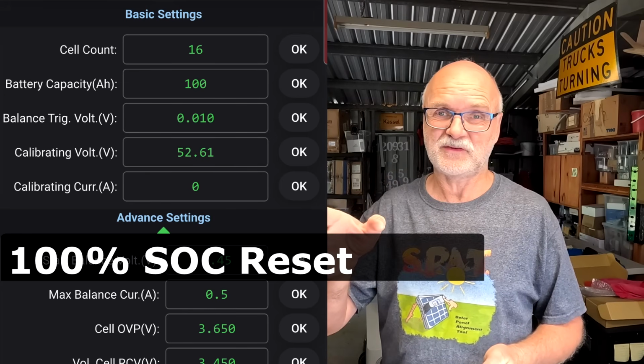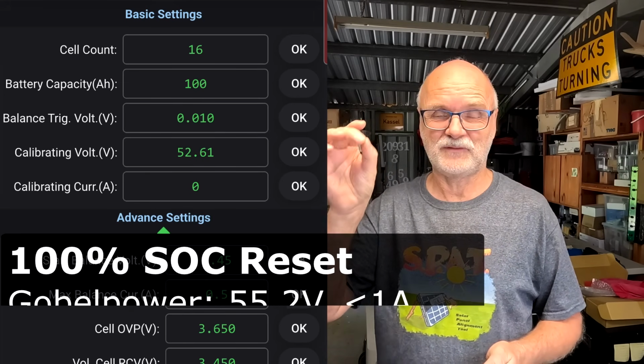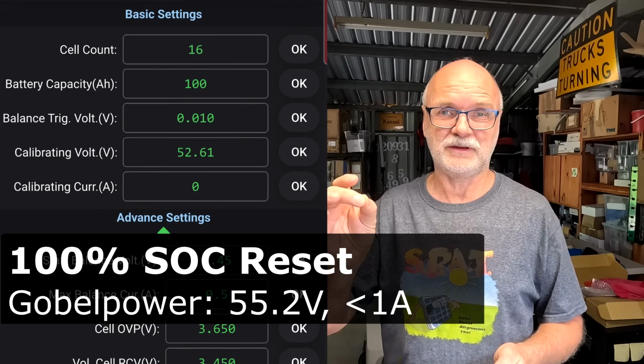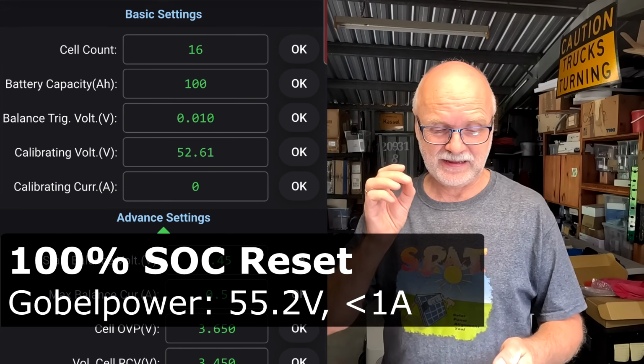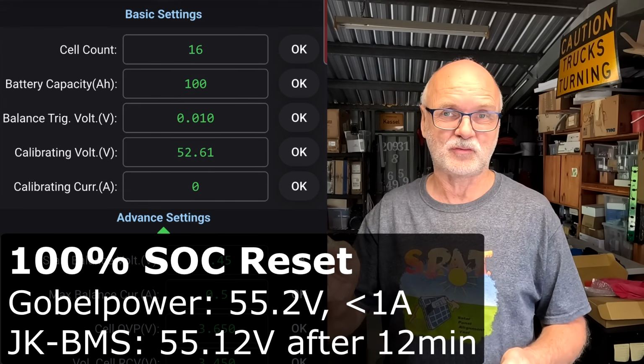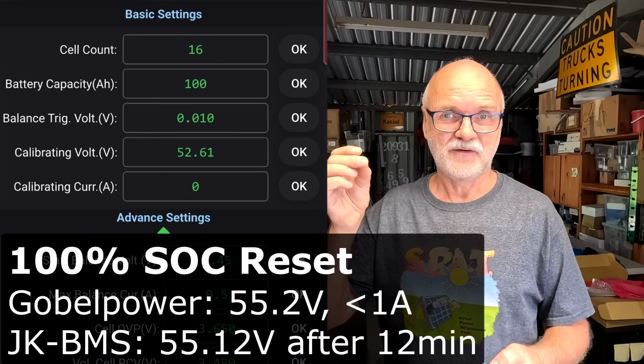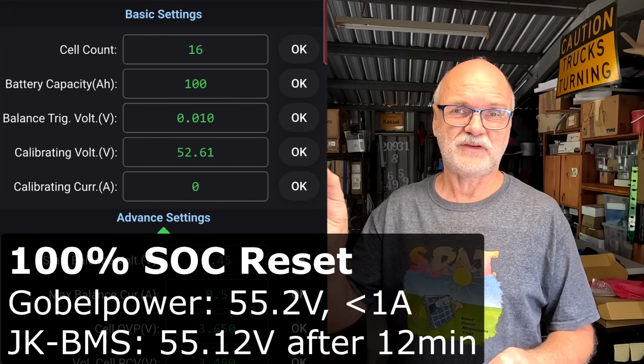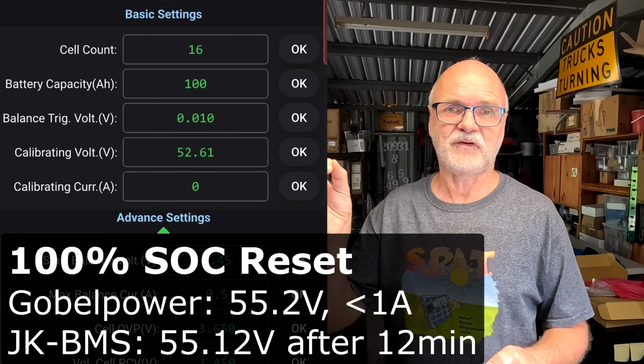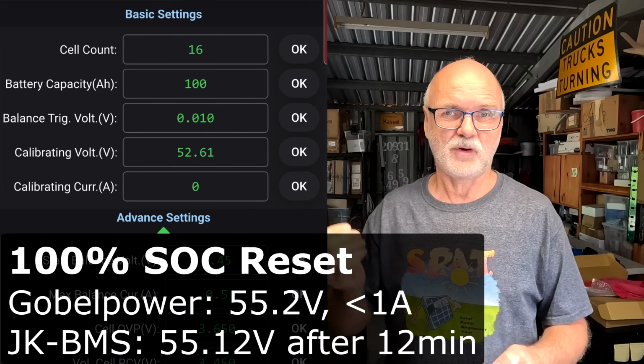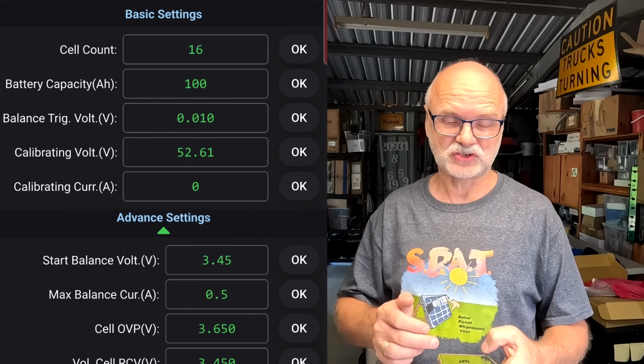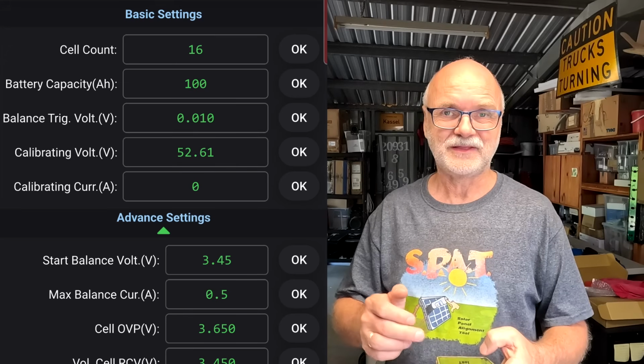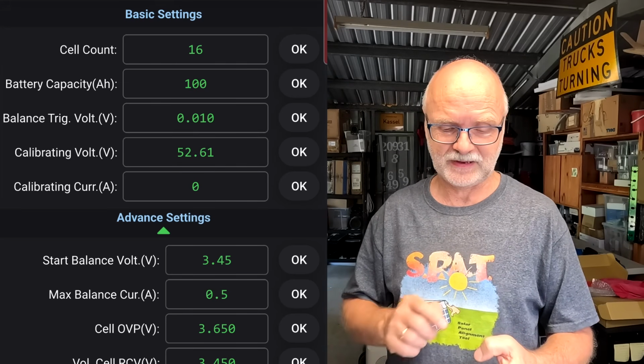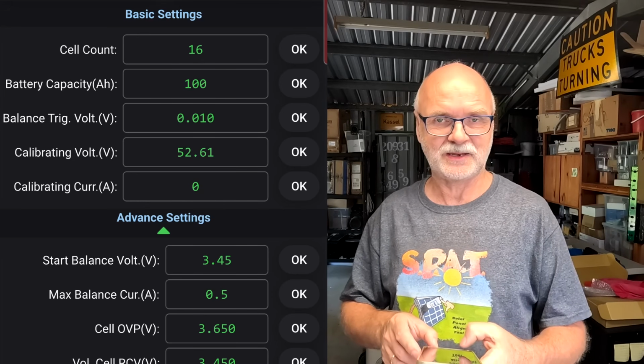So the Gobel Power BMS will reset to 100% at 55.2 volts if the current is under the threshold. And the JK BMS will reset to 100% if the voltage is over 55.12 volts for half an hour, and then the battery voltage still needs to be over or equal to 55.12 volts. Yeah, this is all set with the state of charge 100% voltage.